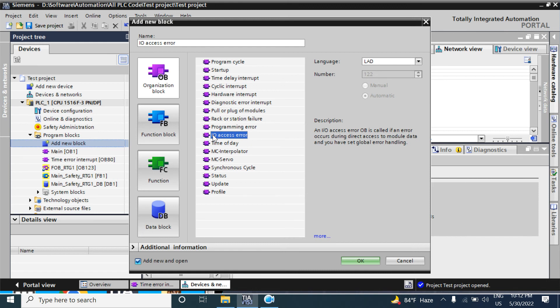The next OB is IO Access Error. This OB is called when an input or output physical address is accessed but does not exist in your program. If the IO Access Error OB is not present in your program, the CPU will ignore the error and will not go to stop mode.